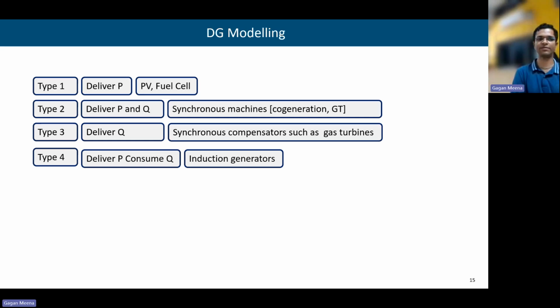Then we have type 3, which deliver only reactive power Q, for example synchronous compensators or synchronous condensers, and they operate at zero power factor. Type 4 are those which deliver active power but consume reactive power, and these are induction generators.